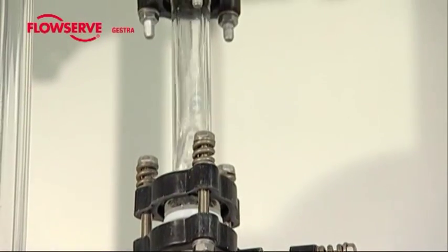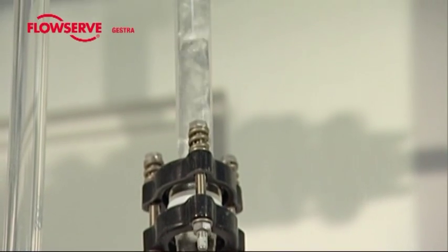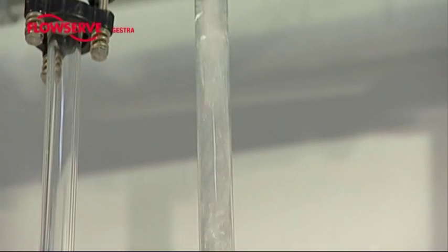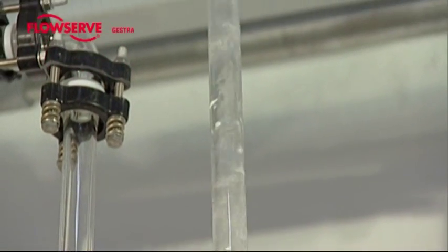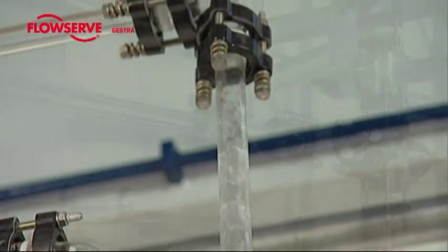The shutoff valve must be opened very slowly to ensure that the number of steam bubbles passing into the water is kept as low as possible. Once the entire body of water has warmed up to boiling point, the steam bubbles condense at only a very slow rate. There is then no longer any danger of Waterhammer.